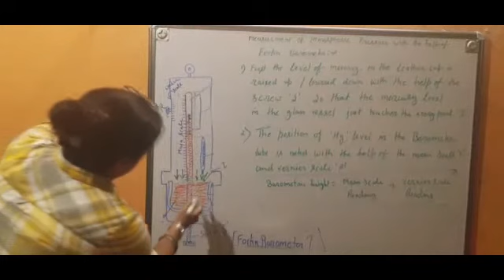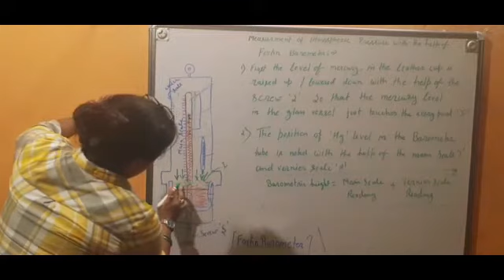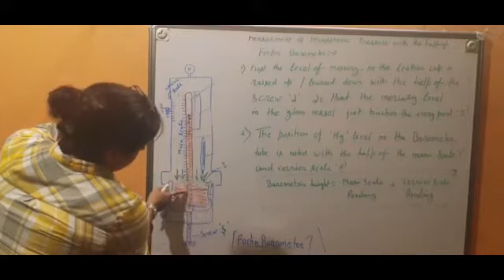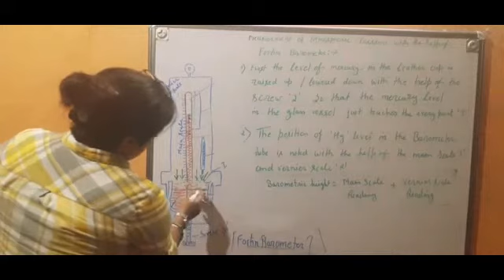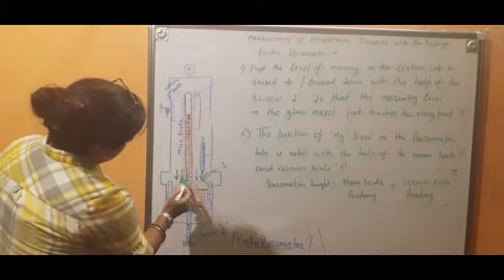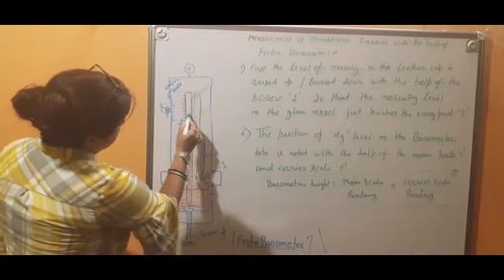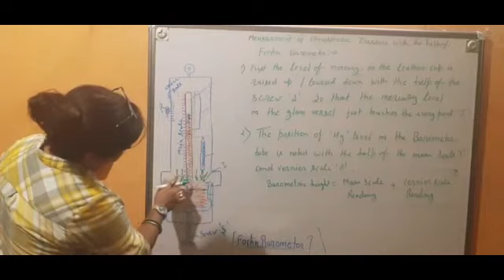So just think, if it is lowered, maybe the level is here, not there. So what you will do, you just use the screw and try to bring the level of this liquid up with the help of this screw, as you can adjust this level. And the condition is that it must match with 0 of your scale, because reading starts from here and you have to read up to which level it touches. So with the help of the screw, if it is lowered, bring it upper, or if it is above 0, bring it lower up to 0.0.